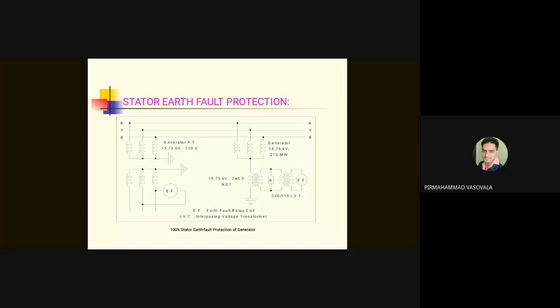Some of the protections are so useful that the blackout that occurred in the northern grid, northeastern grid and eastern grid in 2012 initiated with load encroachment in the distance relays, and ended with probably the pole slipping protection operation. That is, the generator started getting disconnected from the bus due to the operation of pole slipping relays. So pole slipping protection, which we have to discuss in generator protection schemes, is also a very useful protection. And we will talk about all these protections at the relevant time.